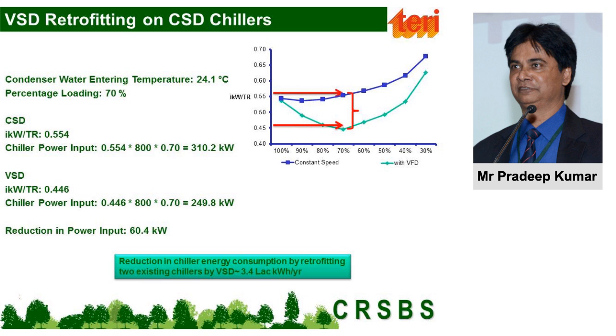Now this is the curve of the variable speed chiller. So this is the difference, that it will come down to 0.45 at 70%, at the same condenser water in temperature and all. And the variable speed chiller will take only 250 kilowatts. So there's a reduction, for this particular case, from 310 to 250, which means 60 kilowatt per chiller.